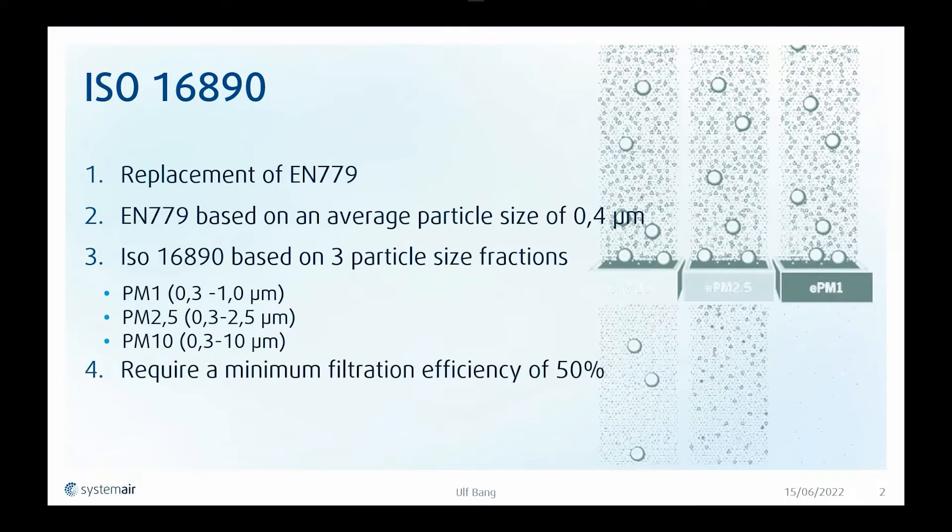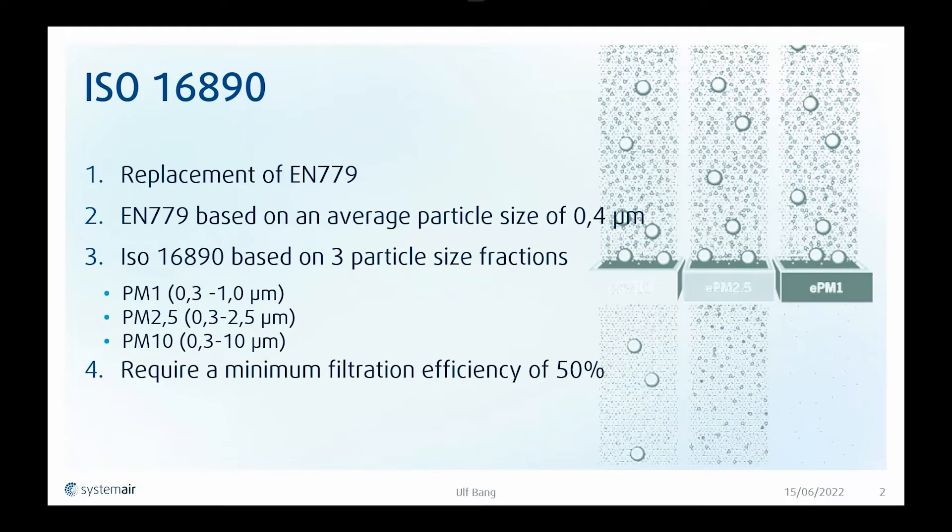It requires a minimum filtration efficiency of 50% to be classified within these three categories. And there is actually also a fourth category. If the filter is less than 50% efficient on PM 10 particles, then it will be classified as a coarse filter.